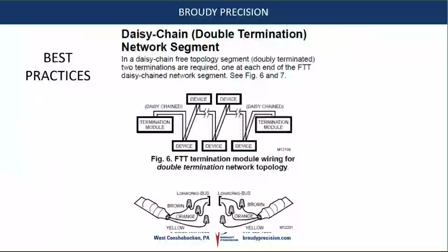This is what I meant about termination modules. We sell a Honeywell flavor of terminating module, shown here on the bottom with the brown and orange terminator - those are the 2 wires used for the doubly terminated setup. If you were going to have a singly terminated network, you'd use the yellow wire along with the brown, used more in a star or T-tap or another topology. But in my experience, this doubly terminated daisy chain network segment is going to be our most resilient network.